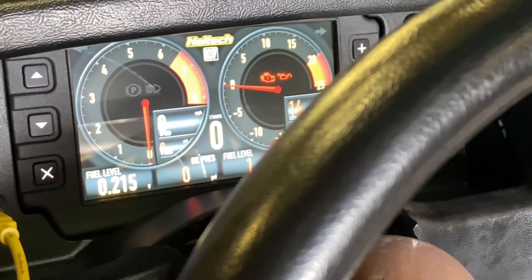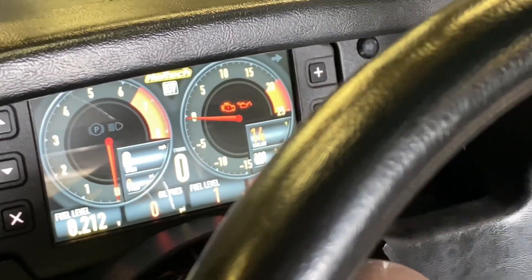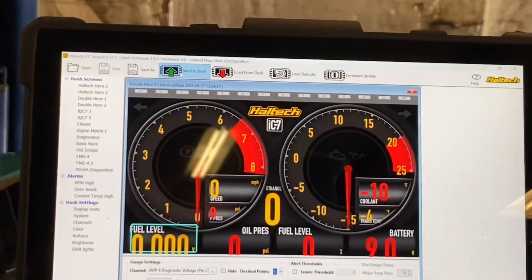It's hard to see, but at dead empty we're about 0.21 volts. We don't want dead empty to actually be at zero — we want to put some gas in it. So we don't want zero to be at zero. Let's put two gallons of gas in it and we'll call two gallons of gas zero. We'll put two gallons in it, see what this voltage is, and then set that as our zero spot.